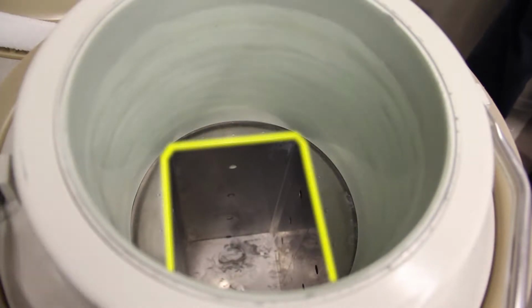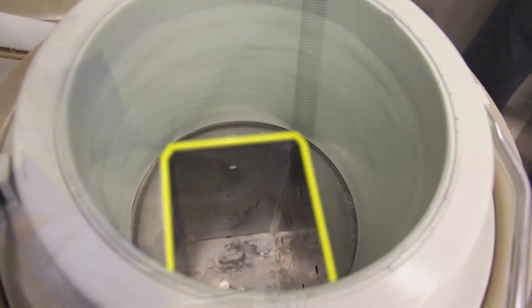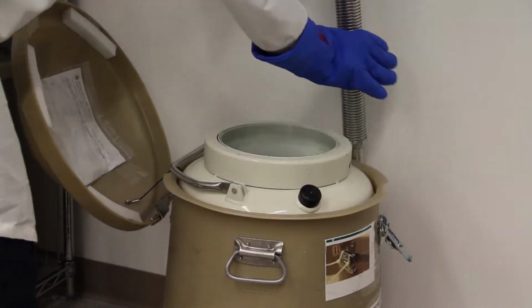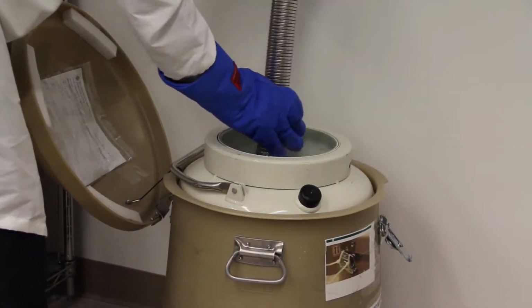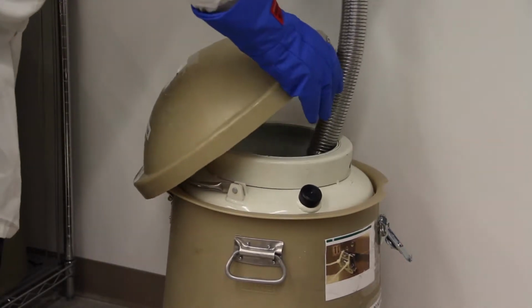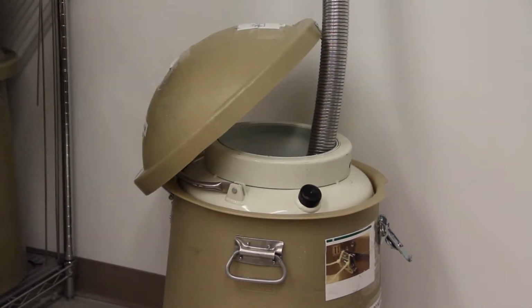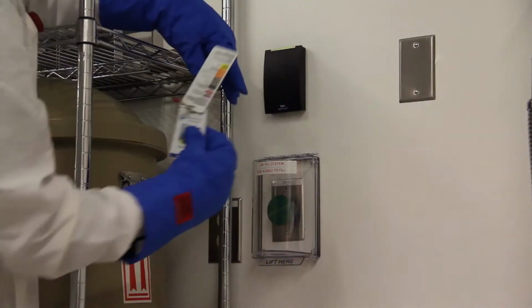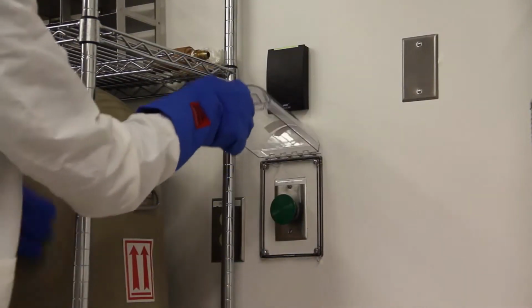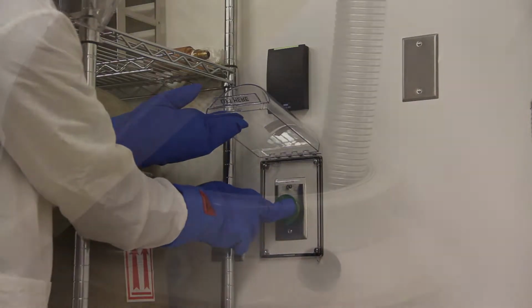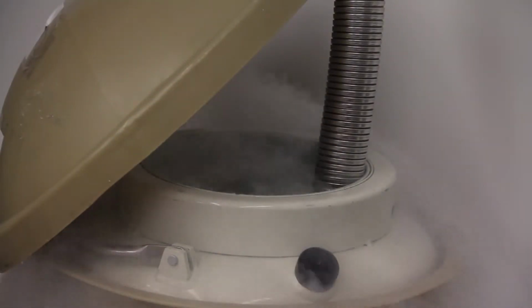The liquid nitrogen should not exceed the edge of the square metal rack compartment or overflow into the circular neck of the dewar. Before initiating the flow of liquid nitrogen, place the transfer hose into the bottom of the dewar and close the cryoport hood to subdue any liquid nitrogen splash during filling. Turn on the liquid nitrogen and monitor the fill progress to ensure the liquid nitrogen does not exceed the fill line.